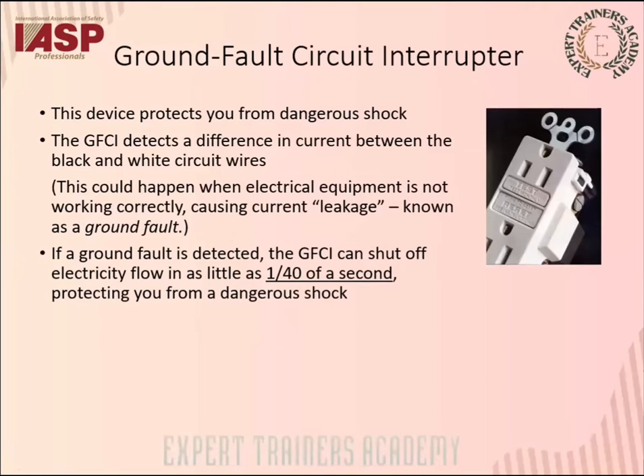Ground fault circuit interrupters. This device protects you from dangerous shock. The GFCI, ground fault circuit interrupter, detects the difference in current between the black and white circuit wires. This could happen when electrical equipment is not working correctly, causing current leakage. If a ground fault is detected, the GFCI can shut off electricity flow in as little as 1/40 of a second, protecting you from the dangerous shock. That means you will still receive a minor electric shock, even with earthing. It's all to reduce the consequences of the electric shock. So the earthing and GFCI, all these are protective systems.